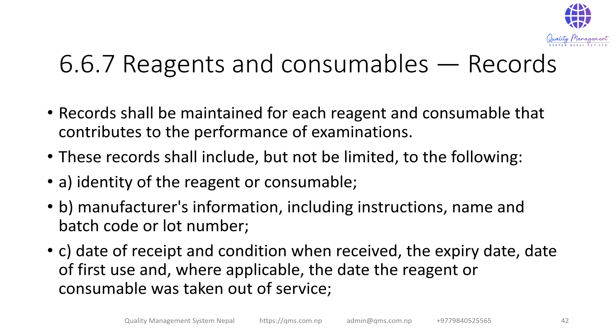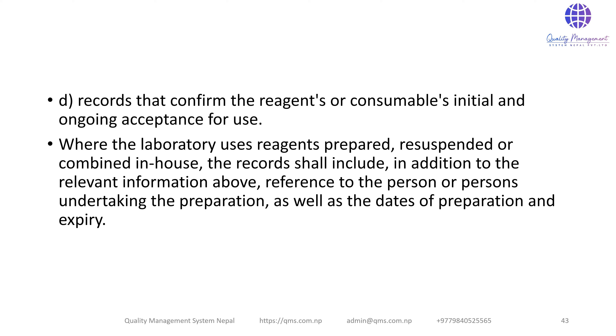6.6.7 Reagents and Consumables Records: Records shall be maintained for each reagent and consumable that contributes to the performance of examinations. These records shall include: identification of the reagent or consumable; manufacturer information including name and batch or lot number; date of receipt and condition when received; expiry date; date of first use and, when applicable, date taken out of service; and records confirming initial and ongoing acceptance for use. Where the laboratory uses reagents prepared, resuspended, or combined in-house, records shall also include the person undertaking preparation, as well as dates of preparation and expiry.